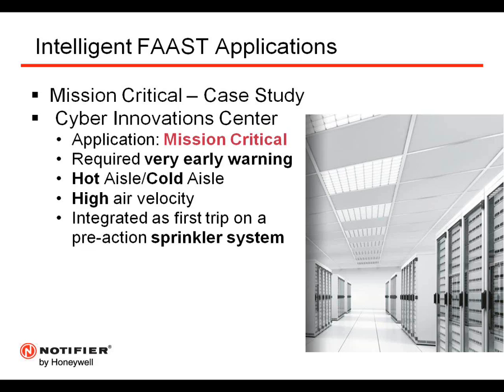So as you can imagine, this is a very high airflow environment, and what they did was they deployed two FAASTs in the cold area of the data center and then also two FAASTs above the exhaust of the hot aisle in the return air path back to the CRAC unit. So it was a very high air velocity application, and they actually integrated the FAAST as the first trip on a pre-action sprinkler system.